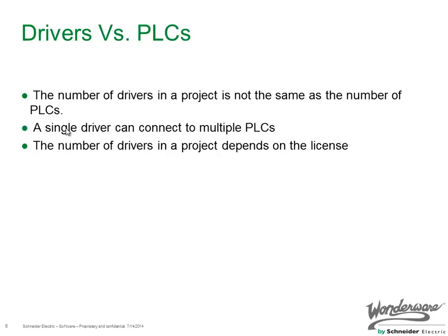So let's talk a little bit about this real quick before we create a project. The number of drivers in a project is not the same as the number of PLCs. What do I mean by that? A single driver can connect to multiple PLCs. You might have a connection to 2 or 3 or 6 or 10 or 16 different PLCs. The limit really depends on the PLC, the architecture, the network, things of that nature.